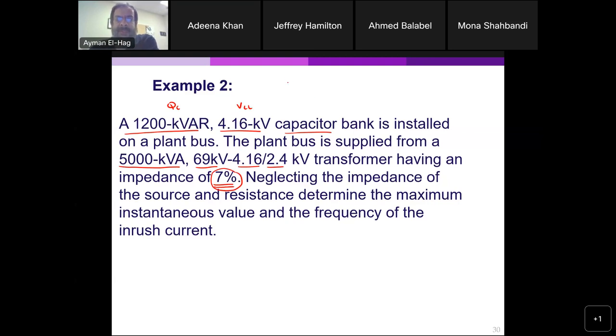Now, what is this 7%? 7% is the impedance of the transformer, or the X of the transformer in per unit. So basically, X of the transformer is equal to 0.07 per unit. Now what is the per unit? The per unit equals X_T actual over X_T base. And the base value we calculate from the rating of the equipment. So the X base is nothing but V squared divided by S. Here V, the line to line, is 4.16 kV, and S is your 5 MVA. That is your base value. So if I want to find the actual impedance of the transformer, you multiply X base times the per unit value, as we will see.